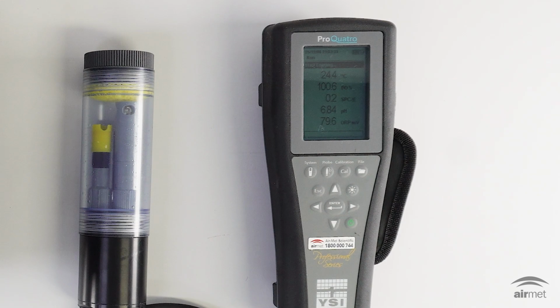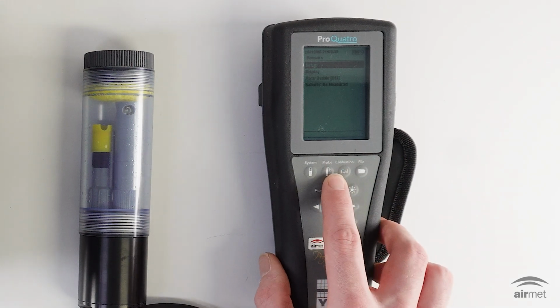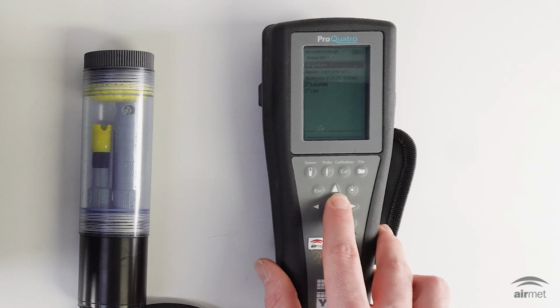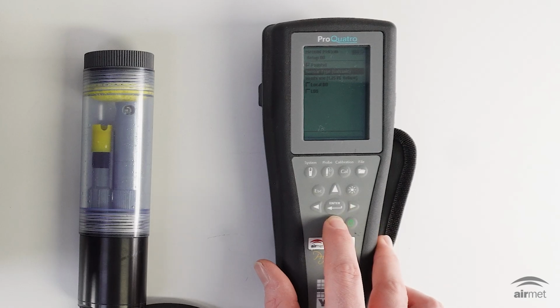The YSI ProQuatro supports both galvanic and polarographic DO sensors. In the instrument setup, ensure the sensor type is correct and matches the installed sensor probe. Galvanic DO probes come with a grey body. Always confirm with the specific sensor label or model number on the probe itself.